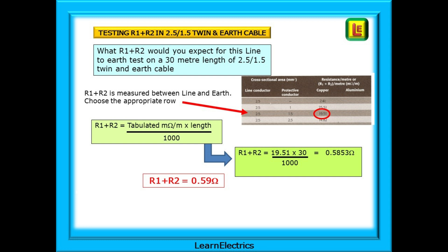The resistance, the R1 plus R2 in this case, is the tabulated milli-ohms multiplied by the length and then divided by 1,000 to convert it back into ohms, what we should see on our test meter. So 19.51 milli-ohms multiplied by 30 meters and divided by 1,000 gives us 0.5853 ohms. Rounding up, we can say that R1 plus R2 is 0.59 ohms.